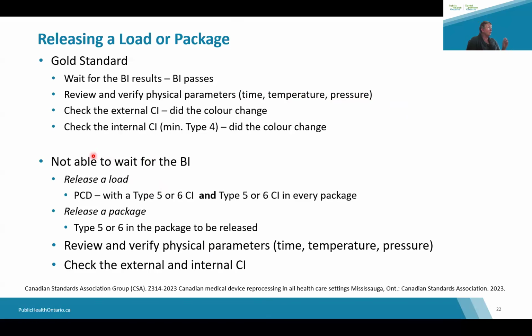And then you're also going to check the external chemical indicator, did the color change? And then you're going to check the internal chemical indicator, a minimum of a 4, but better to have a 5, and did the color change? But if you're not able to wait for it, then there is a way that you could release a load.